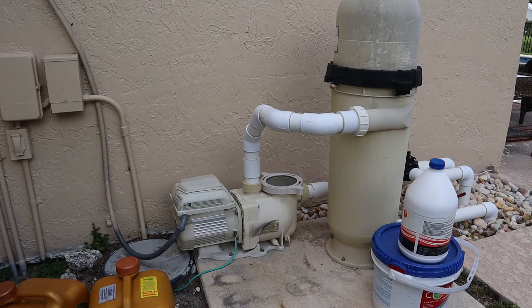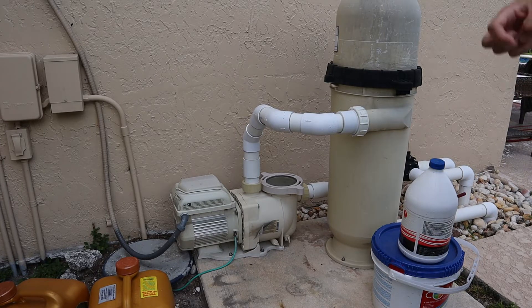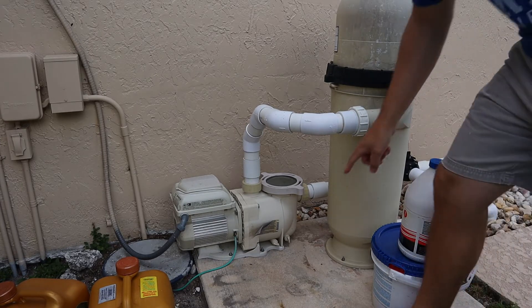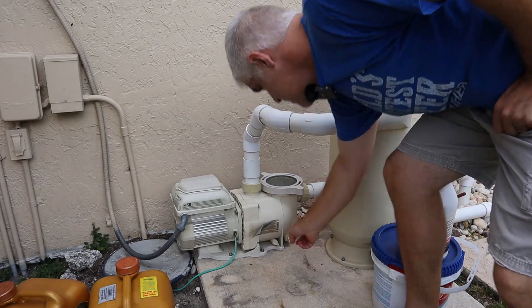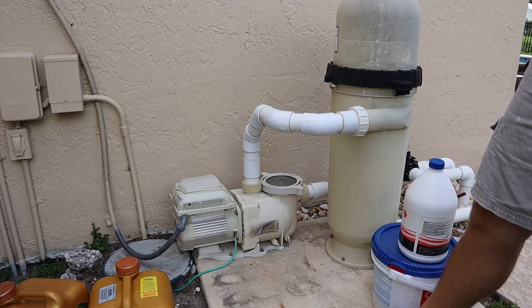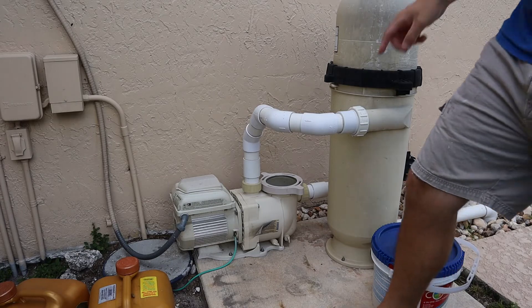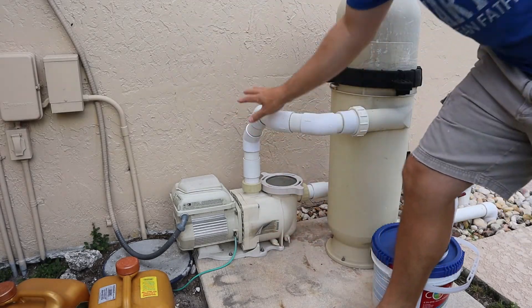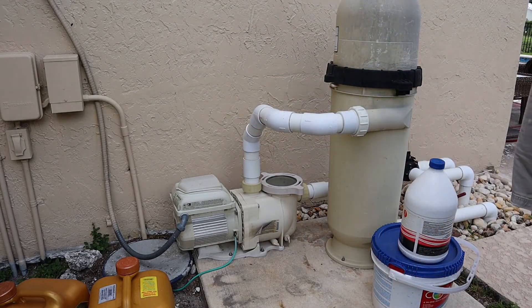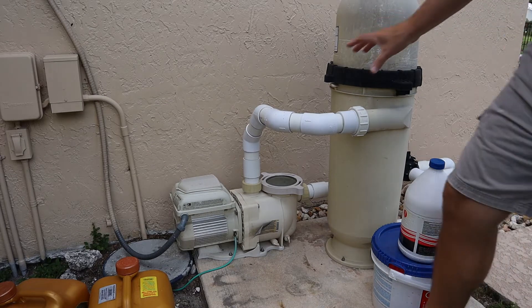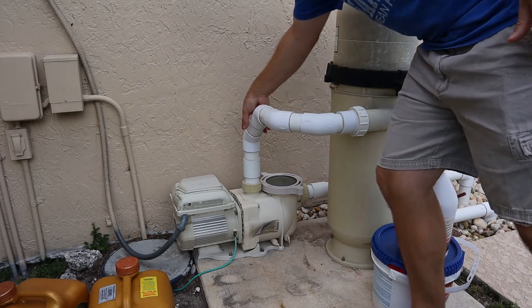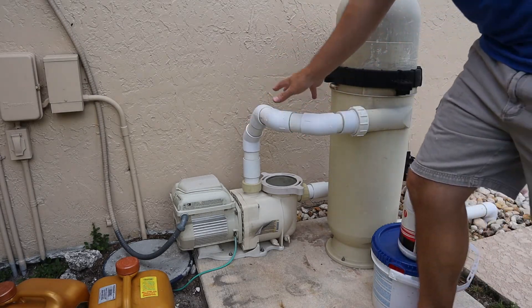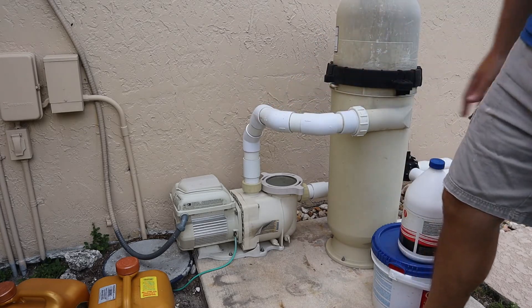But there's another way. You can measure total dynamic head using a vacuum gauge on the suction side, that port is right here, and also a pressure gauge on the output side, which is right here, which should be very similar to the pressure gauge on your filter.